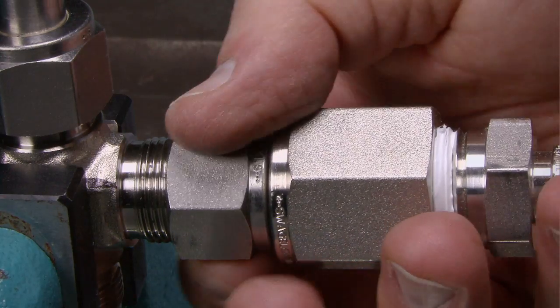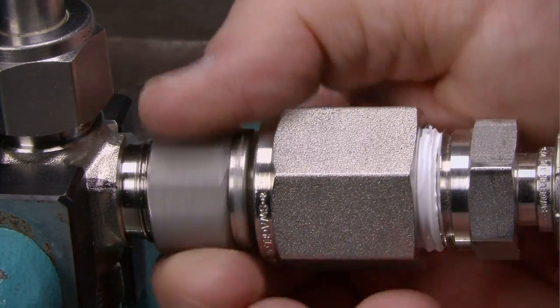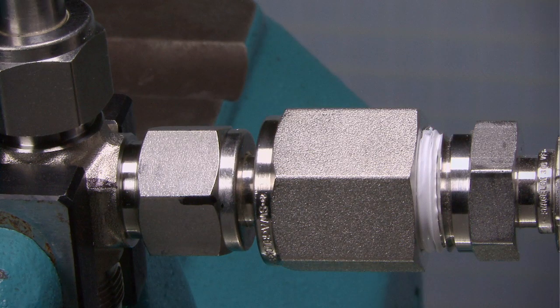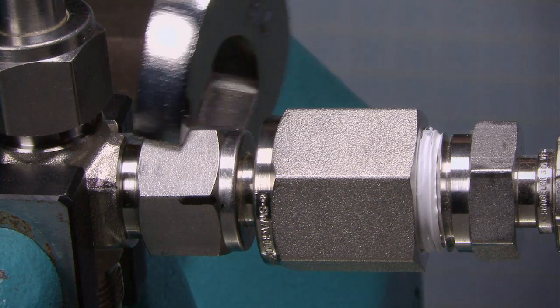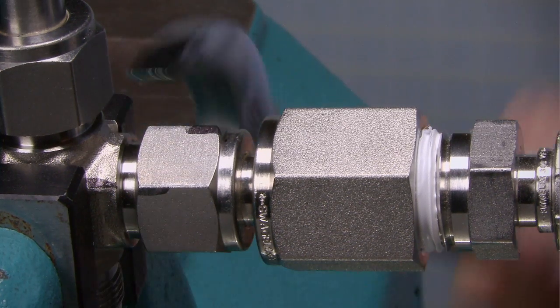Insert the tube with pre-swaged ferrules into the fitting until the front ferrule seats against the fitting body. While holding the fitting body steady, rotate the nut with a wrench to the previously pulled up position, as indicated by the marks on the tube and flats.